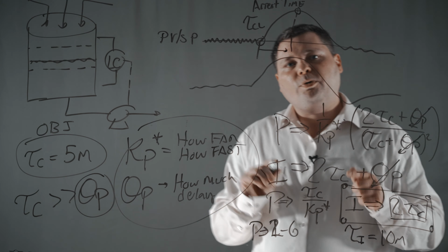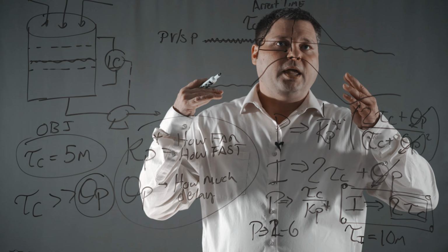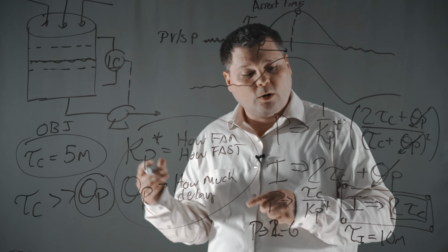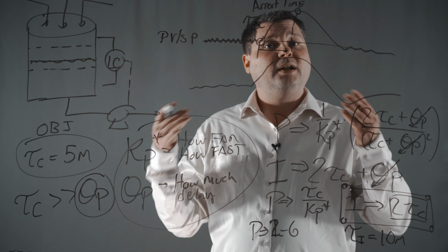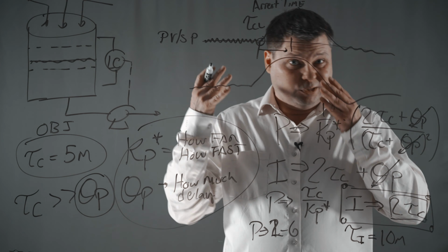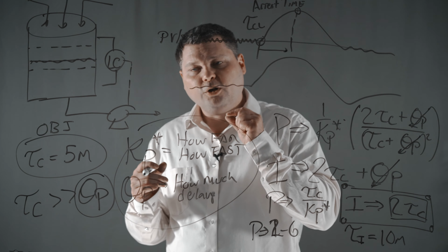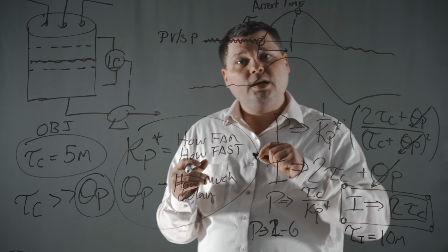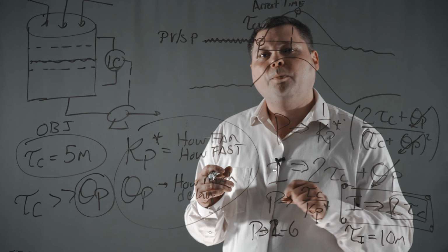If you're dealing with reset rate, which is going to be in the numerator, or independent forms of the PID equation, where it's not the dependent form, your integral terms tend to be very, very small. So if you're using an independent form in Rockwell, for instance, your Ki could be 0.0001 in some cases. So level controllers tend to be a little bit finicky when tuning. They also tend to be the most often requested loop from customers that we help them tune.